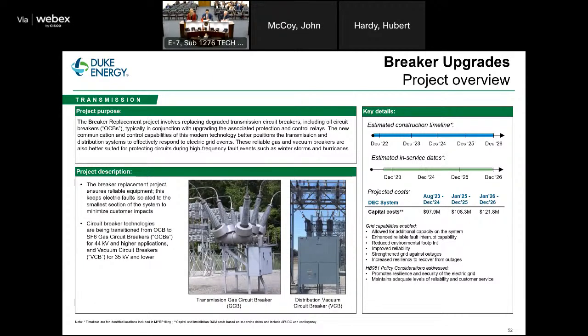The last point on this slide I'll mention is we are specifically targeting the circuit breakers and prioritizing them. So we're looking at end-of-life assets. We're prioritizing based on field inspection, so the actual condition of the breaker, electrical testing that we perform periodically, the configuration of that breaker and redundancy. So if the breaker fails, do we have a direct customer outage or do we have built-in redundancy? So that factors into prioritization.